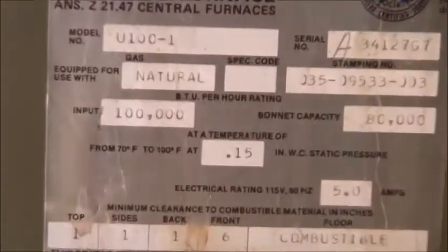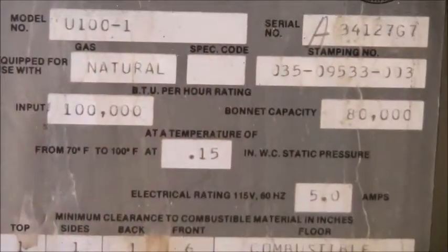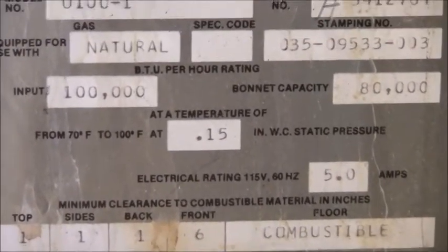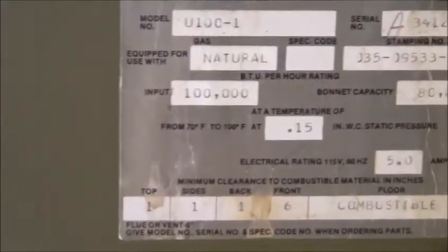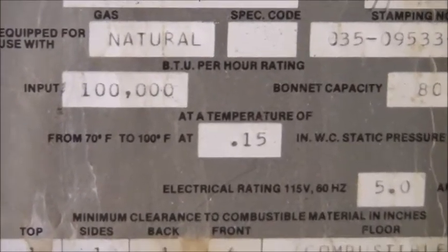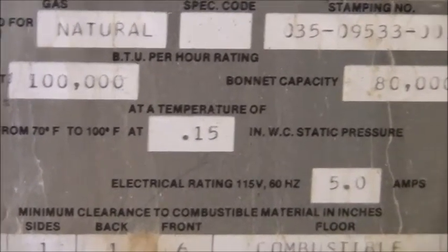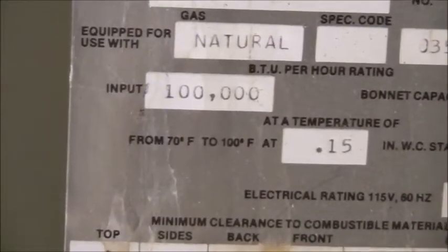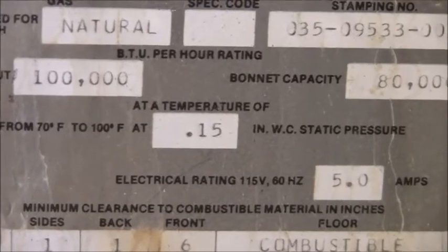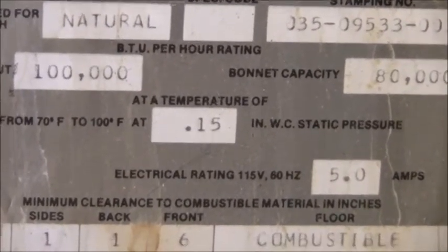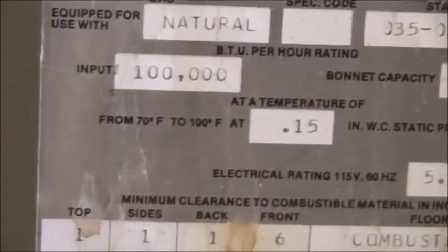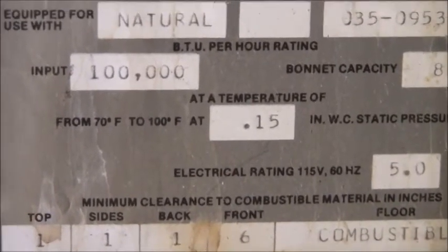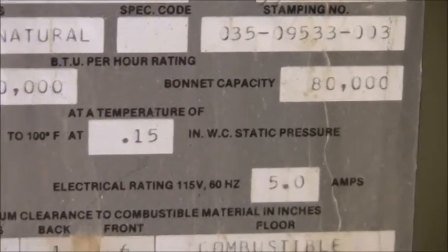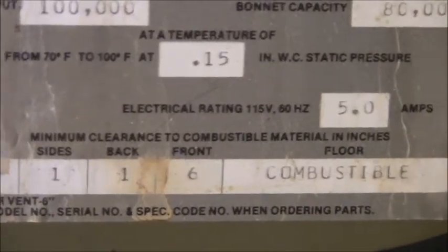Now, on the furnace right here, there should be information about the rated external static pressure, but it doesn't have it. This just tells you the heat rise from 70 to 100 degrees at 0.15 inches of water. That's how much temperature rise we should get with a .15 inch water column static pressure. I'm unclear if that's a supply static pressure or exactly what static pressure that is. And then there's your electrical rating right there.